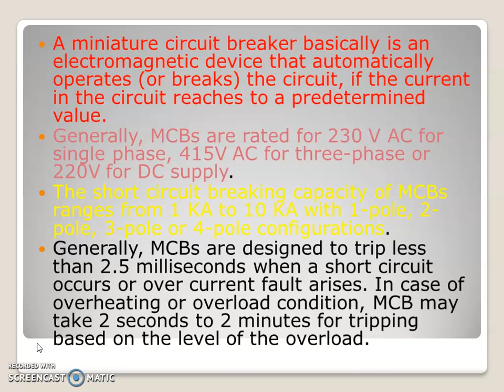Generally MCBs are designed to trip in less than 2.5 milliseconds, meaning MCB trips the circuit within 2.5 milliseconds when there is a short circuit in a circuit. In case of overheating or overload condition, MCB will take 2 seconds to 2 minutes depending on how severe the overload is. Right, meaning depending on how many seconds, how many minutes, or how much overload there is on that system, on that circuit, the MCB will trip the circuit during the overload condition.